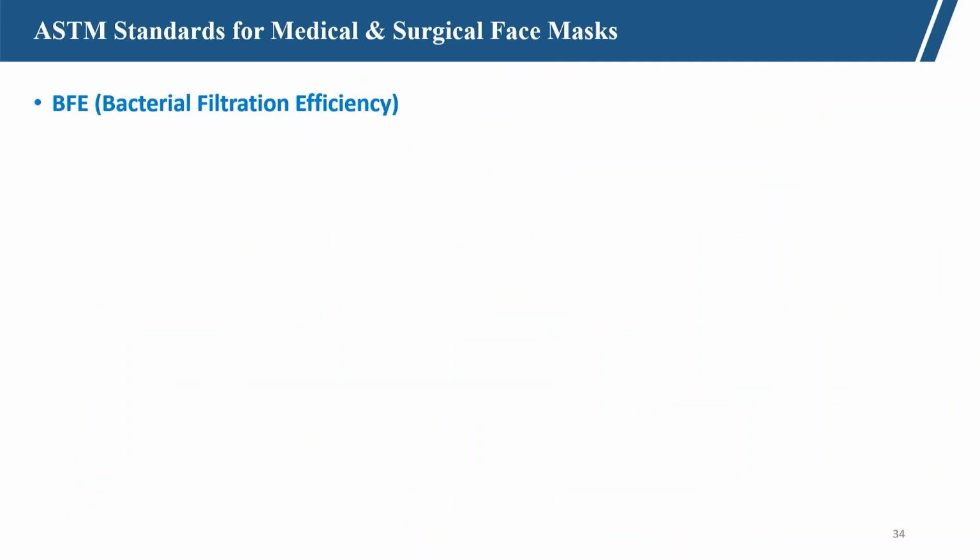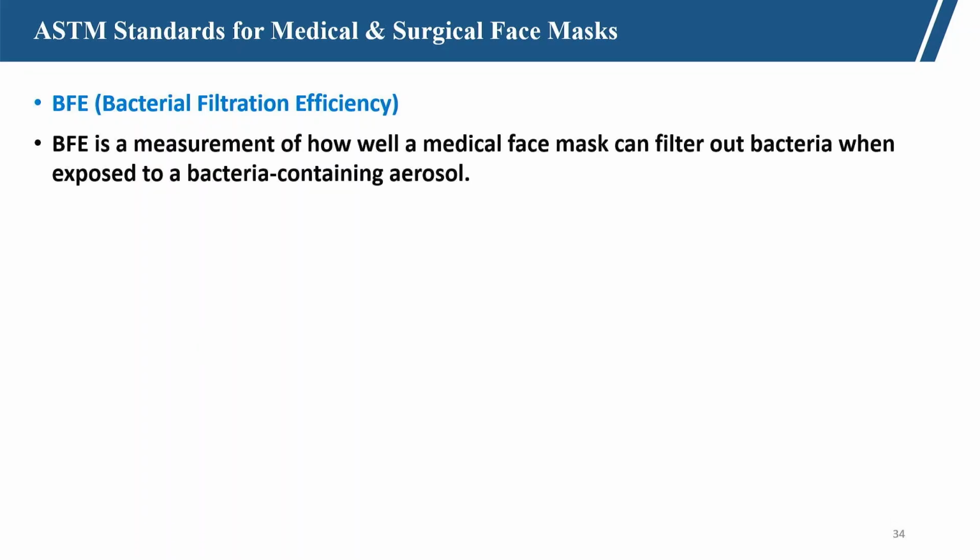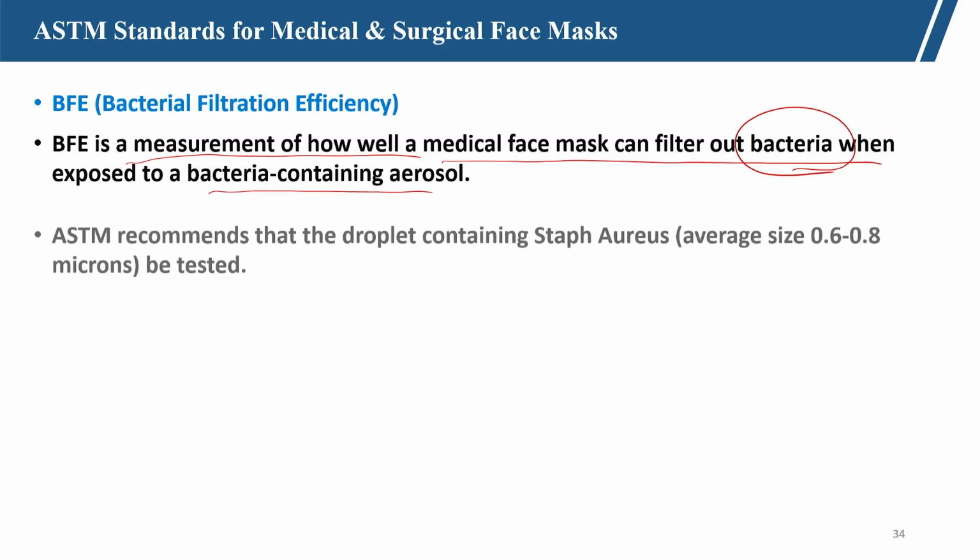So, let us see what bacterial filtration efficiency testing, BFE, is. BFE is a measure of how well a face mask can filter out bacteria when exposed to a bacteria-contaminated aerosol. The aerosol is contaminated with bacteria, and how well the mask filters it out is tested.